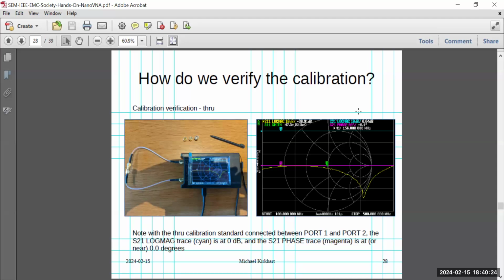Okay, so now when we have the through calibration standard on, we're not so concerned about the Smith chart, but it should still be in the center because again, port 2 should be terminated in a 50 ohm load. So it should be a pretty good match. But the things you want to look at are the S21 log mag. This should be pretty close to 0 dB or something like it, something within decibel dust, as one of the members likes to call it. And if you look over here at the S21 phase, it should be at about 0 degrees or something close. Once you get through all that, it's like, okay, I got a calibration. I got a measurement plane that's right here at the connectors. Now I can go forth and measure DUTs. And guess what? We get to go.